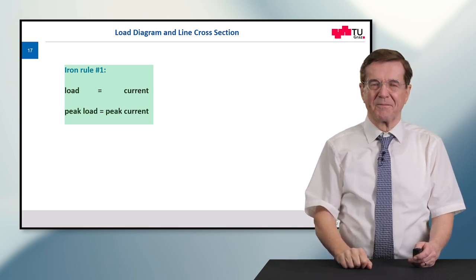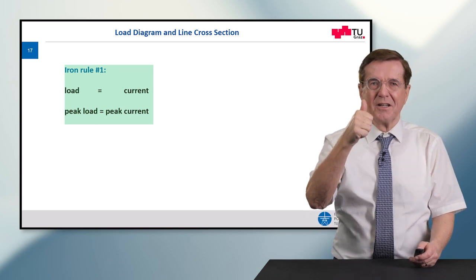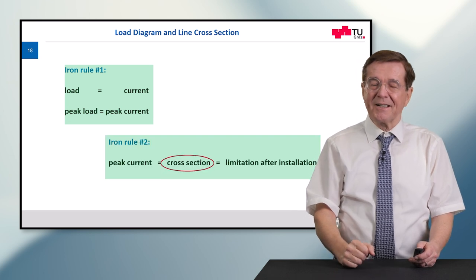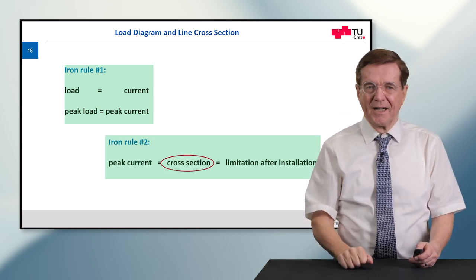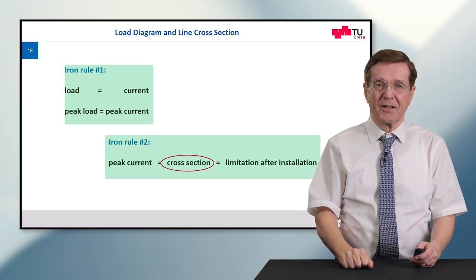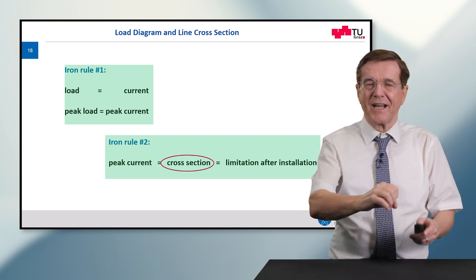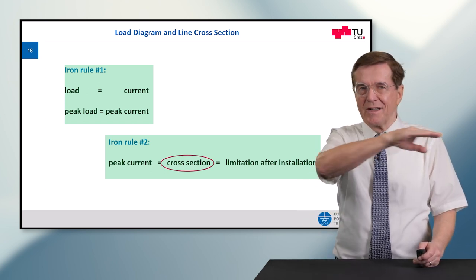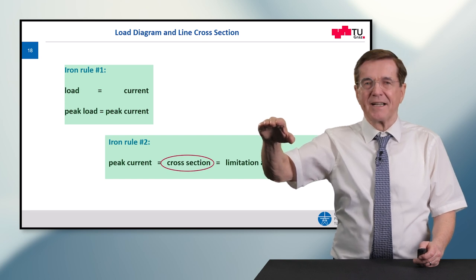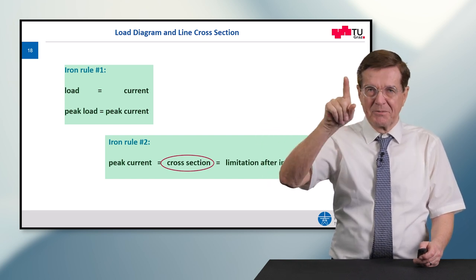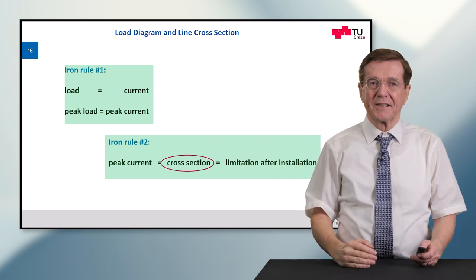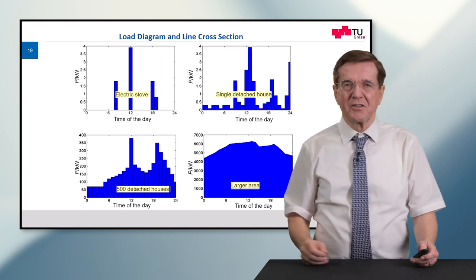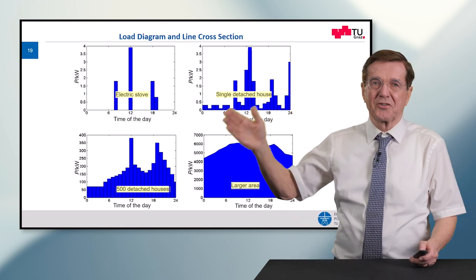There are two iron rules which lead to the construction of electric networks and which must be observed. Iron rule number one: load is current and peak load is peak current. Iron rule number two: the peak current determines the cross-section of the cable, the line, or the overhead line. Once it is installed we are limited — we cannot extend this easily. So the peak current is the measure for installation purposes.